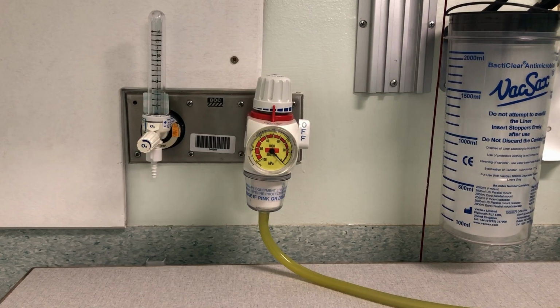Actions to take if there's an error or failure of the device. Remove the device from use after ensuring the patient is safe and unharmed. Complete a clinical engineering decontamination form detailing any error codes or messages. If the device is involved in an incident, ensure that the datix number is recorded on the decontamination form. Ideally return the device to clinical engineering as it was set up and used. If this is not possible, take an image of the setup and ensure this is uploaded to the datix incident form.